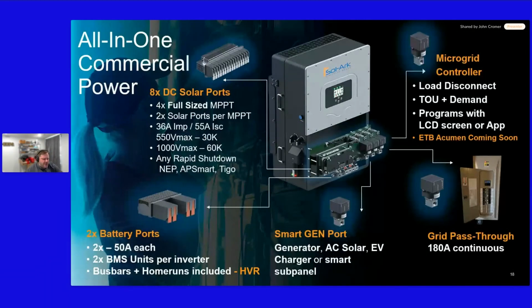If not using the GEN port for AC solar, you can use it for generators or EV chargers. You could even put a sheddable sub panel onto that port, so there's a lot you can do with it. If you're doing a solar powered carport and not putting in EV chargers right away, you now have an interconnection point out there ready for the EV chargers later.